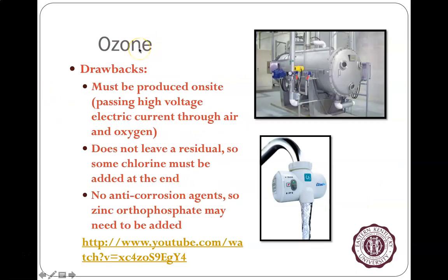Now, why would somebody not want to consider using ozone? So ozone, with all of its good things, does require a lot of electricity to generate. It doesn't leave a residual in the system. So it's not like you've got free chlorine that stays out there. Ozone is quick to be made and it's quick to disappear. So it can only disinfect for a brief period of time, and then you'd have to add more. And the corrosion associated with ozone, especially at the water plant, can be pretty potent. So you have to replace a lot of things or have very strong anti-corrosion control methods.